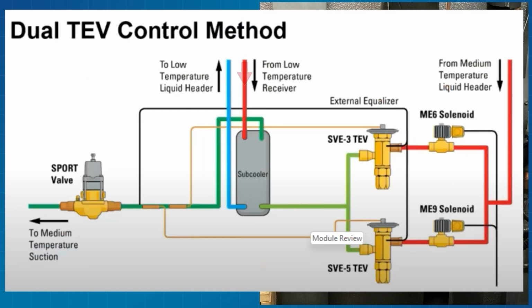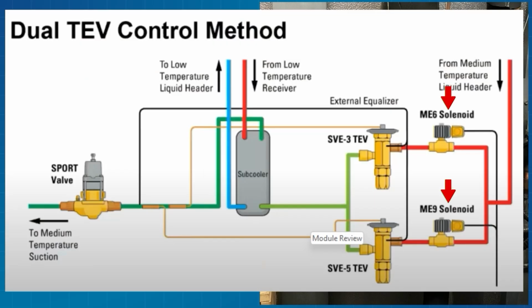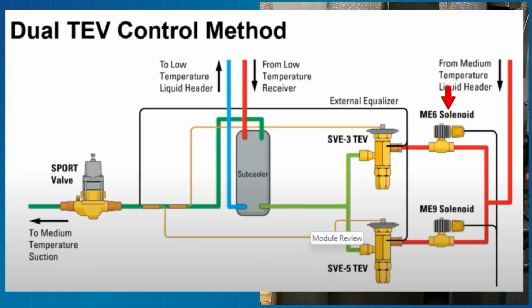For that circuit, my refrigerant is coming in here and coming out chilled. It's just that simple. Now, the way this is gonna stage, if I'm gonna have a cut in and cut out for this solenoid, let's say my target is 50 degrees subcooling. I'm gonna set this valve, this solenoid, to open when the liquid leaving temperature, this blue pipe, hits 50 degrees, warming up.